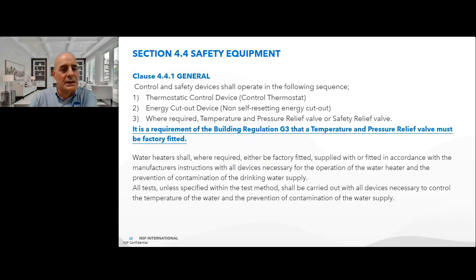Clause 441 of the standard then covers the general requirements. Control and safety devices shall operate in the following sequence. First, the thermostatic control device or the control thermostat must operate. Secondly, then, the energy cutout device or the non-self-resetting energy cutout must operate. And third, then, where required, a temperature and pressure relief valve or safety relief valve. It is a requirement in the building regulations that a temperature and pressure relief valve must be factory fitted.